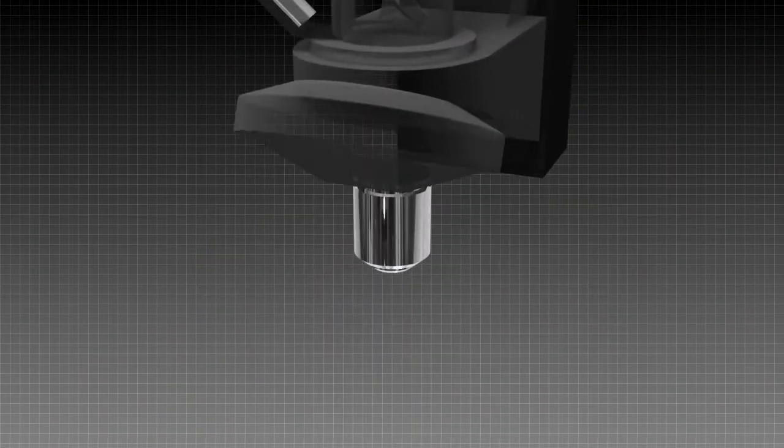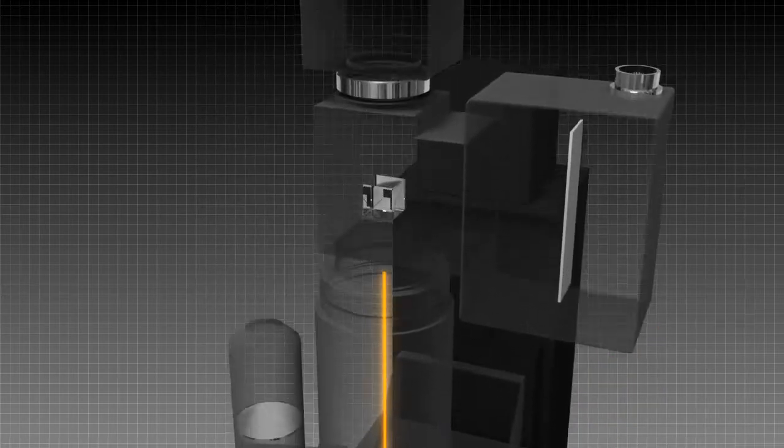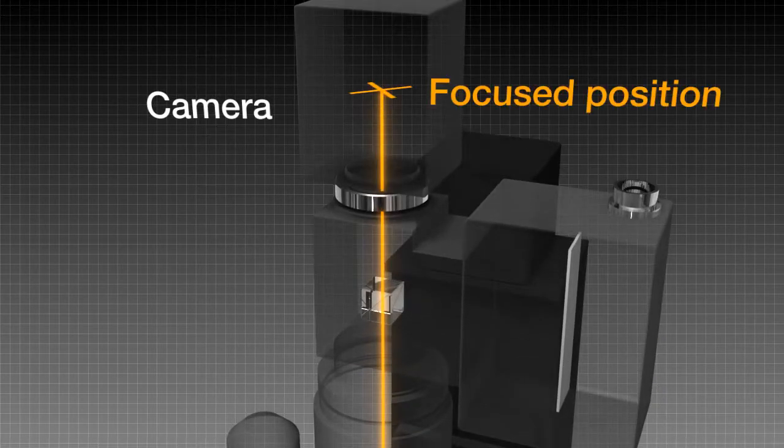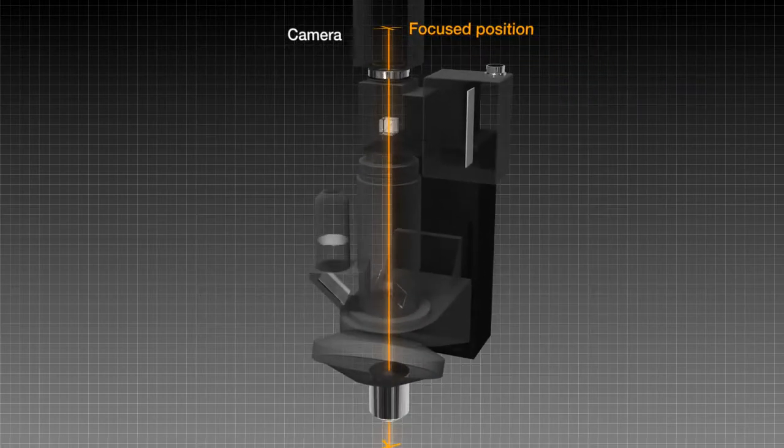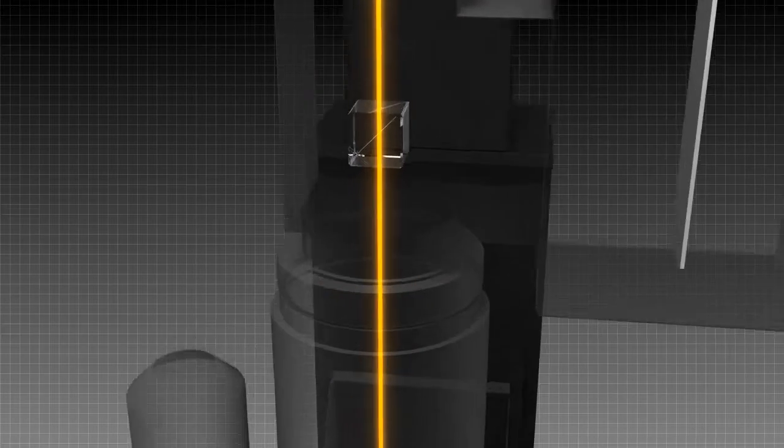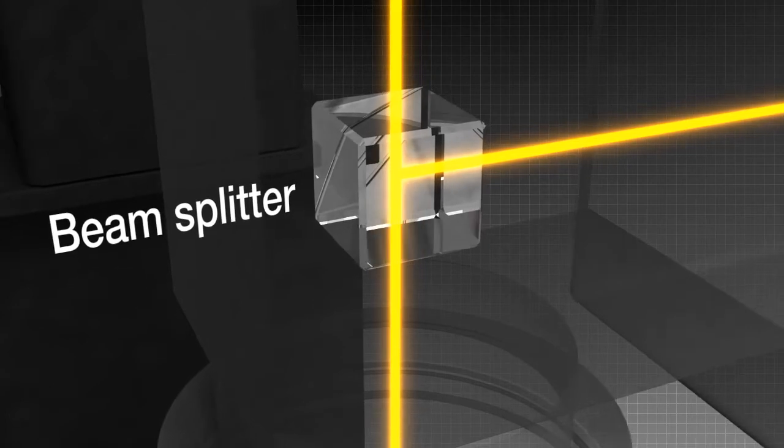First, when the objective lens focuses on the target object, it sends the image to an imager, such as a CCD camera. The signal used for autofocusing is split off towards the line sensor from the video signal by means of a beam splitter located just before the camera input.